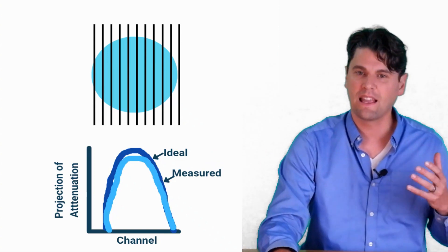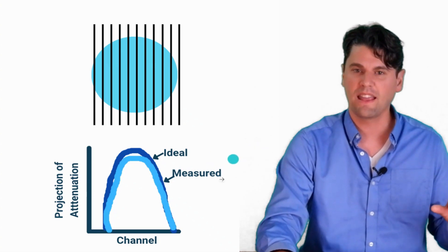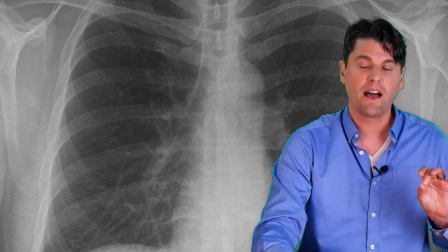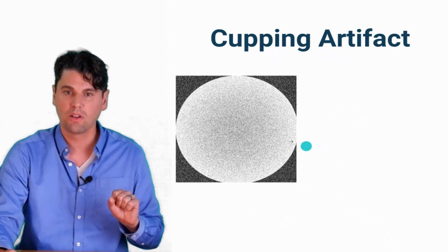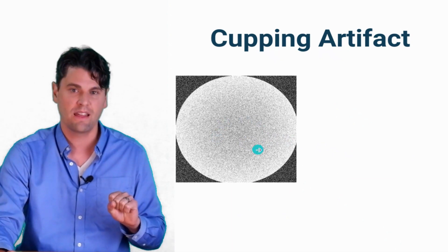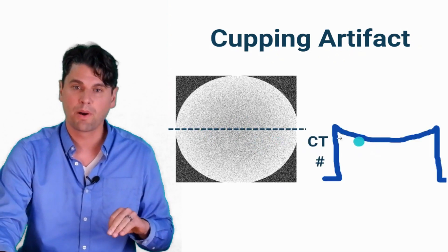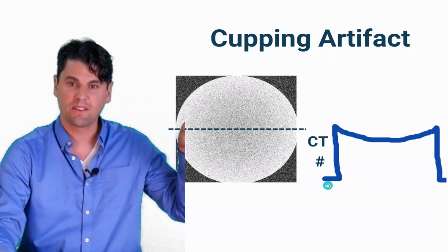If we try to make an image using filtered back projection, we take the signal, filter it, and back project it into the image. Because the projection values in the center are a little bit lower than they should be, the CT values in the middle of the image will also be lower than they should be. We call this a cupping artifact. If you draw a line through the image and look at the line profile — the CT number along that line — there's a dip in the middle that looks like a cup.